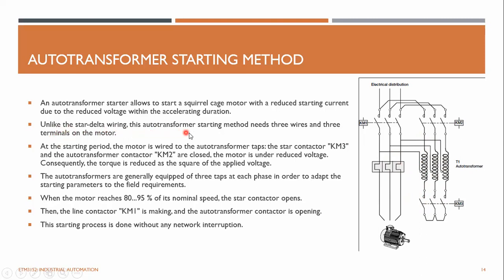Unlike the star delta wiring, this auto transformer starting method needs 3 wires and 3 terminals on the motor. So you don't need access to all 6 terminals, you just need 3 terminals from the motor, unlike the star delta method. It simplifies the wiring from the motor, but this has to be wired somehow. At the starting point, the motor is wired to the auto transformer taps, the star contactor KM3. So initially KM3 is shorted. Right, KM3 is shorted.